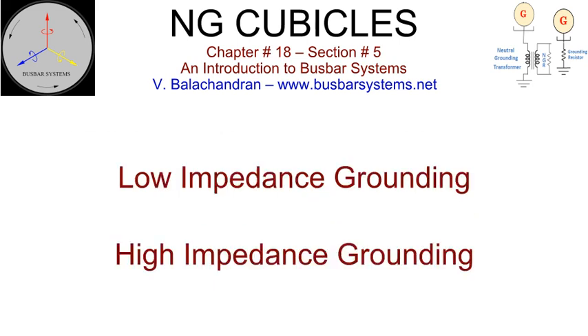All generators' neutrals have to be grounded through an impedance to limit the line to ground fault current to safe limits. Two systems of grounding are adopted for a generator, mainly dependent upon its size. Low impedance grounding, where a generator neutral is grounded through a resistor, is adopted for small unit sizes.